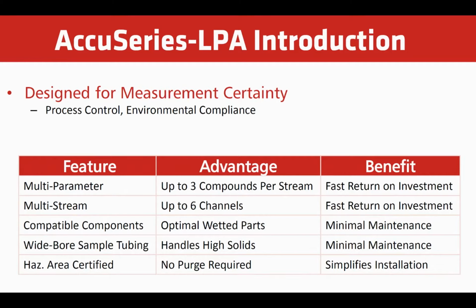We offer the analyzer hazardous area certified for Class 1, Div 2, or Zone 2 ATEX applications without a purge required. So this greatly simplifies the installation and also maintenance. You don't have to bring instrument air out to the unit.